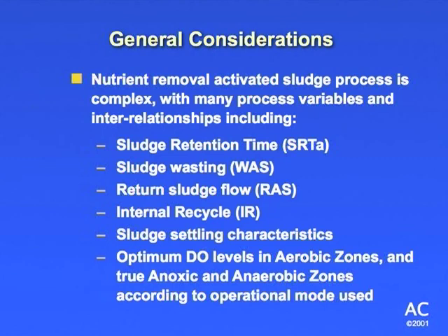Once it goes through and your nitrogen's getting into the aerobic zone, your nitrifiers now come into play. They have the stage. They're using that oxygen and they're going to nitrify like mad. That's where that internal recycle pump comes in to help keep swinging it back up there now and meet the BOD coming in and use that BOD as a carbon source to help drive the denitrification, okay? And we're going to do another review on that as well before we actually start the process up. But that's a good point.